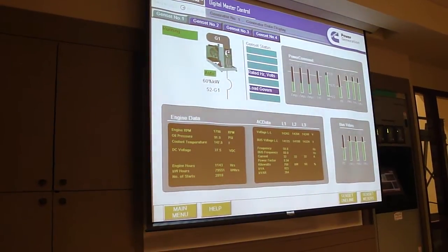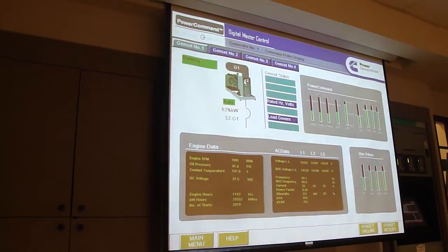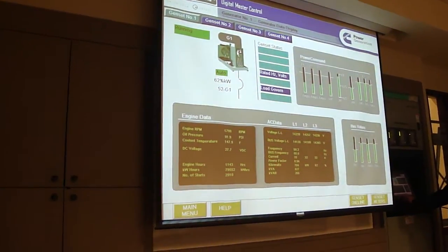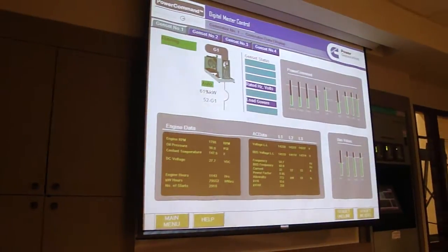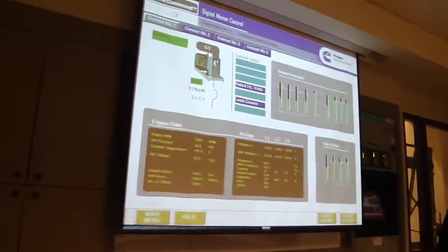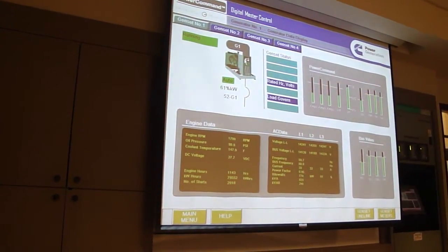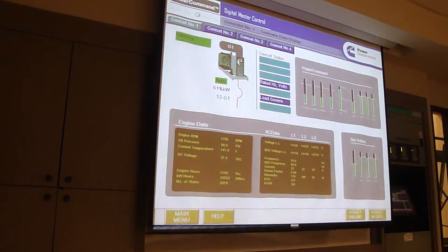That's a lot of operations for a breaker that's probably designed with about 700 or 800 operating operations as a design criteria. As for fuel consumption — diesel consumption — we don't have any fuel consumption readout here. When this was put in, these engines didn't have that. Normally on a standby, nobody cares. If it's a continuous application, it's a big deal, but if it's a standby it matters less.